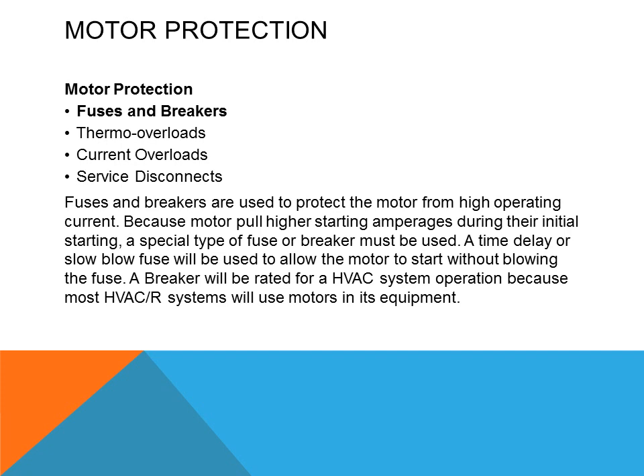Fuses and breakers are used to protect the motor from high operating current. Because motors pull high starting amperage during initial startup, a special time delay or slow-blow fuse must be used to allow the motor to start without blowing the fuse. A breaker used for an HVAC system must also be rated to handle the inrush current during startup without tripping.